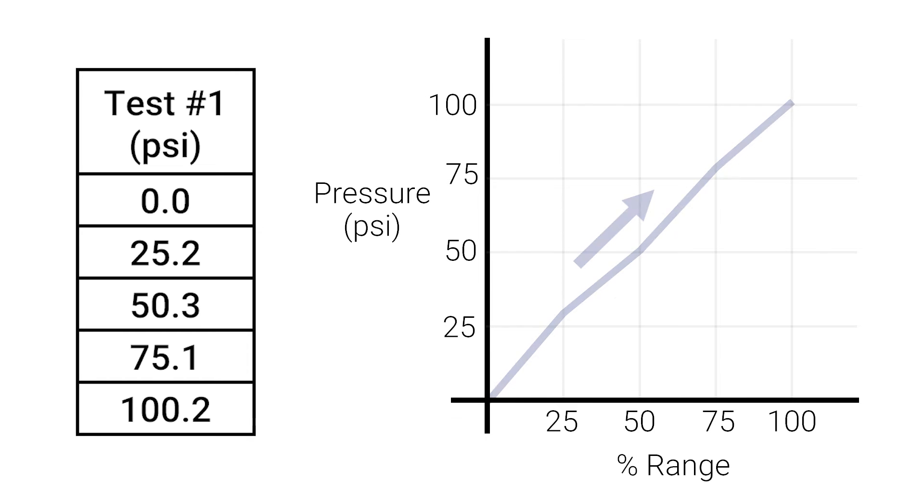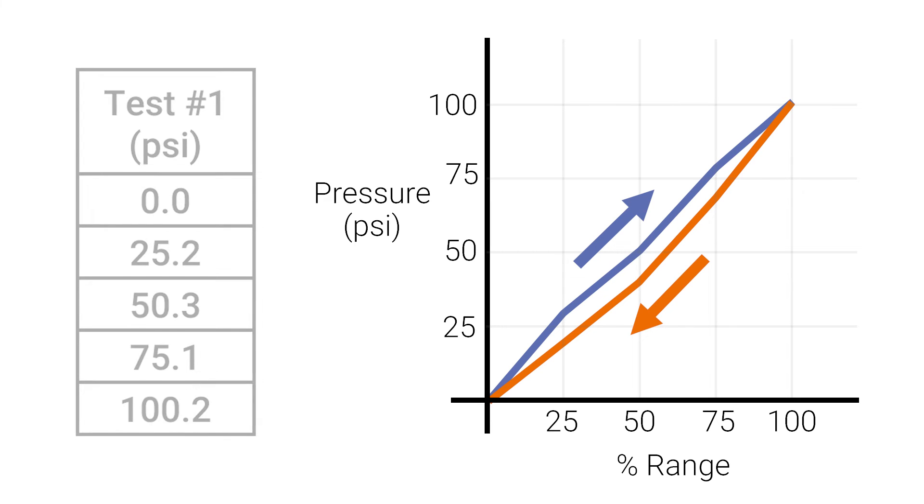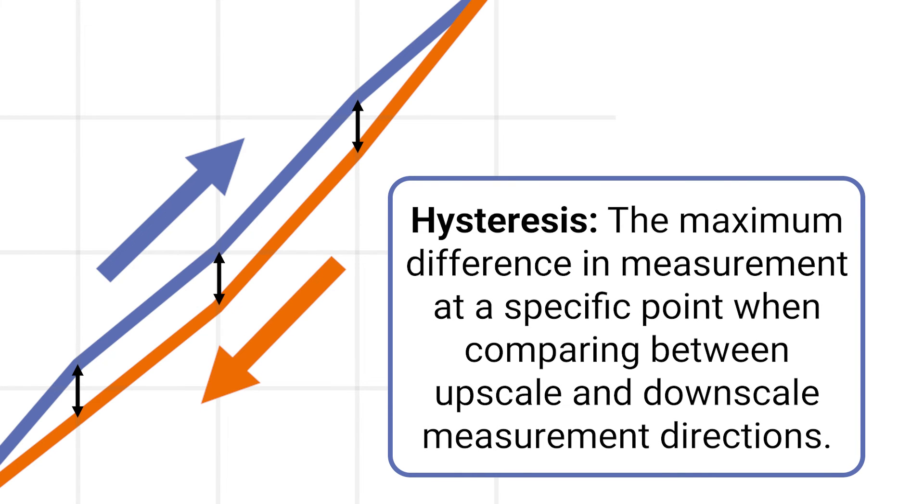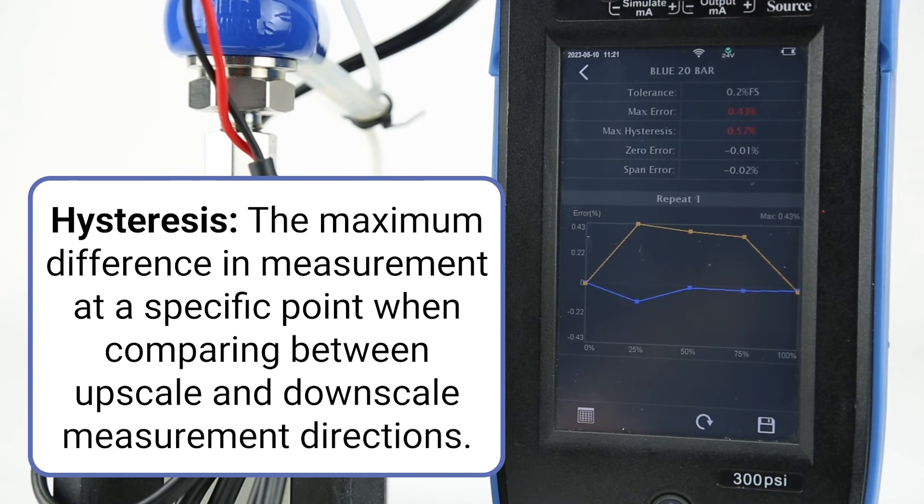When cycling a test like this up and down, the output of the measurement can change depending on the direction from the previous value, for example during pressurization and depressurization. This phenomenon is called hysteresis and must be recorded as it can be a significant source of uncertainty in the measurement.